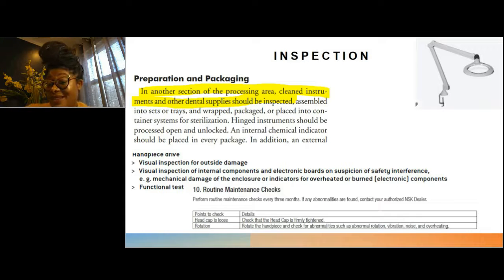So there is something that I did find that was missing in the reprocessing steps, and that is inspection. Inspection is key. As you can see, inspection is required as a guidance. It is a guidance within your CDC, and it's also inside of your IFUs, and it will tell you exactly what it is that you're going to need to inspect.